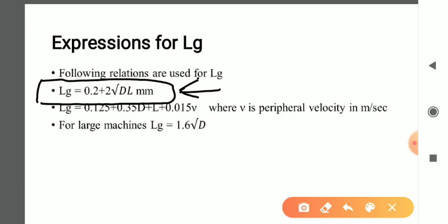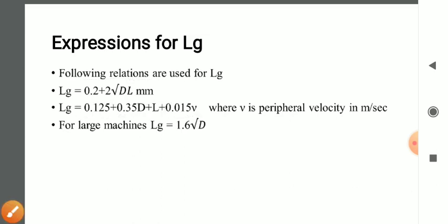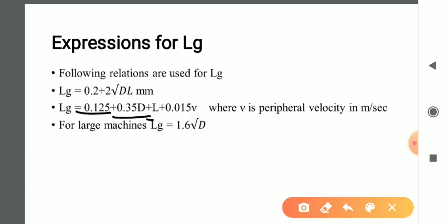The air gap length can also be calculated under certain constraints. If a velocity constraint is given, then you can use: lg = 0.125 + 0.35D + L + 0.015 × v. And in a few cases, if the machine is said to be a large machine, then you can calculate lg by neglecting the length term: lg = 1.6√D.